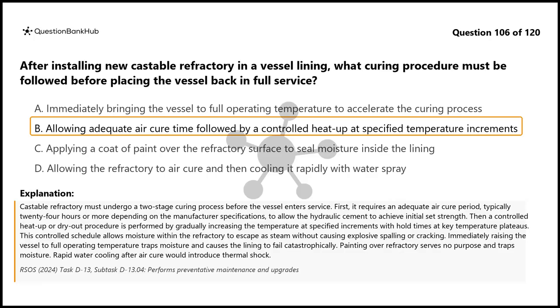Then a controlled heat-up or dry-out procedure is performed by gradually increasing the temperature at specified increments with hold times at key temperature plateaus. This controlled schedule allows moisture within the refractory to escape as steam without causing explosive spalling or cracking. Immediately raising the vessel to full operating temperature traps moisture and causes the lining to fail catastrophically. Painting over refractory serves no purpose and traps moisture. Rapid water cooling after air cure would introduce thermal shock.